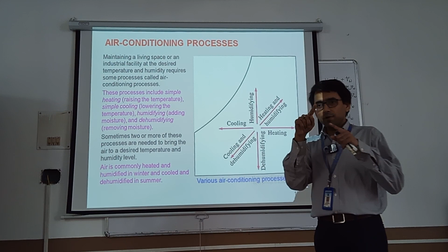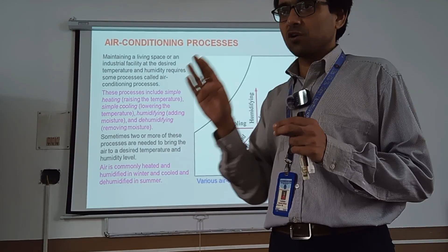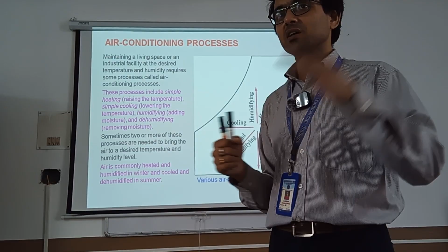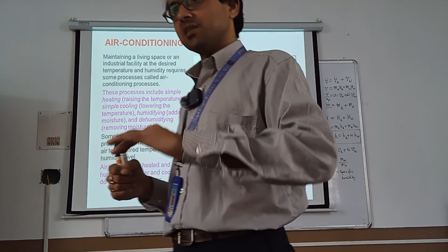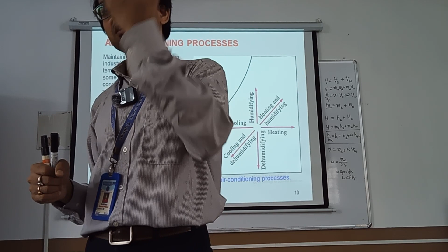This cooling and dehumidification will go together, because when you add a cooling coil and the temperature of the cooling coil is below the dew point temperature, what will happen? Over the cooling coil surface there will be separation of moisture, condensation. If the temperature of the cooling coil surface is below the dew point temperature, the moisture in the incoming air will start condensing, and therefore the moisture will be separated. So now the dehumidification will be done. Is it clear? So cooling and dehumidification are done together, and heating and humidification are also done together.